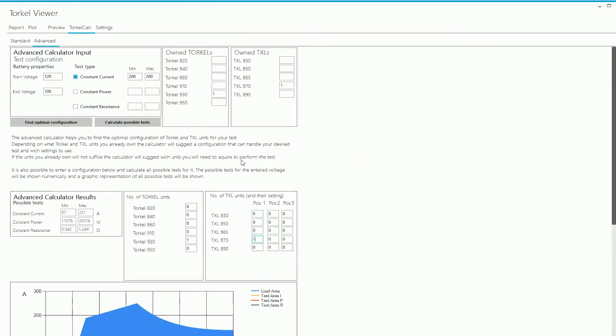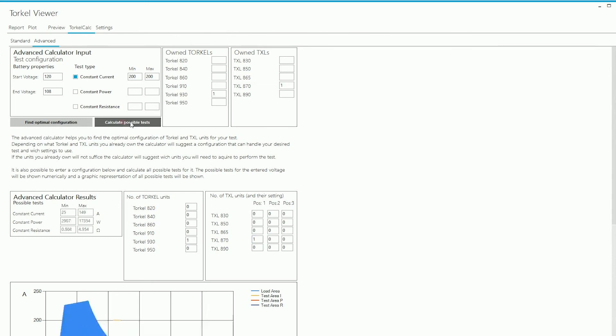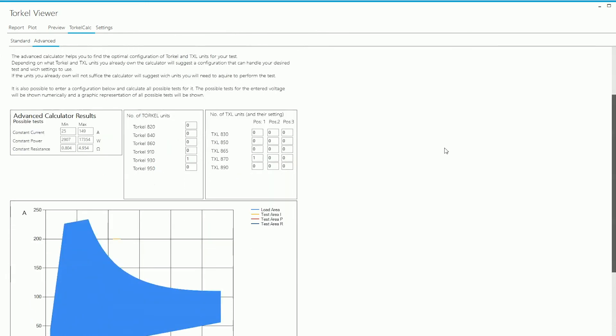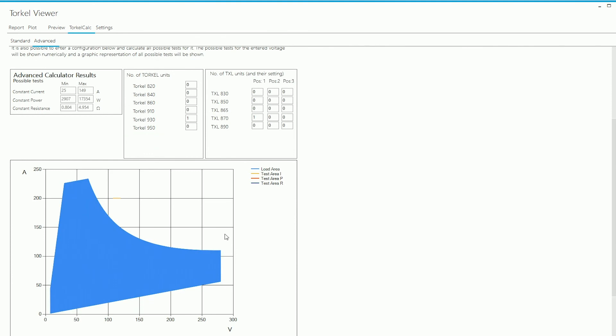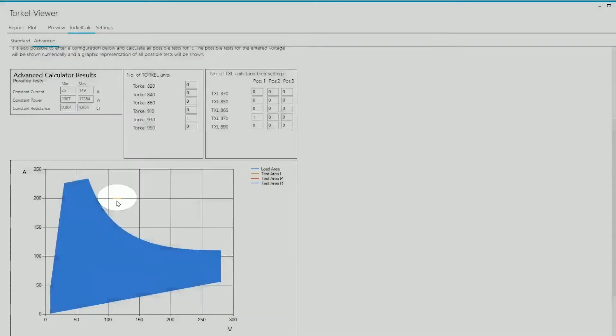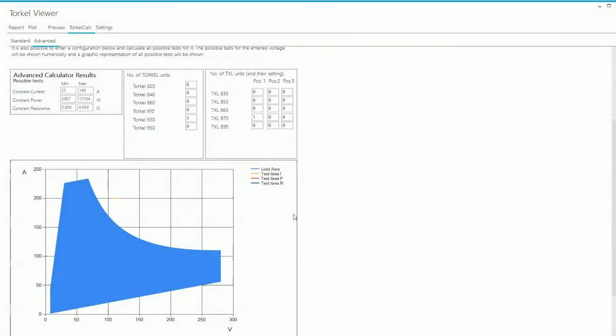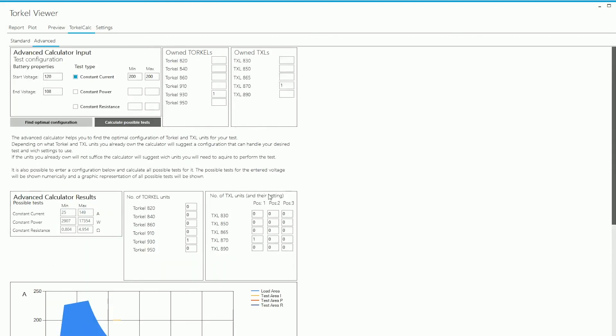I have changed the switch position on the TXL 870 and then I click on Calculate Possible Tests. When I do that, the software shows me the current capability of the configuration that is selected here. It's recalculated here and this time you can see that the test area, which is in fact over here, lies outside the load area. So it's not possible to run the test that I've specified here with one Torkel 930 unit and one TXL 870 if the switch on the TXL 870 is on position one.